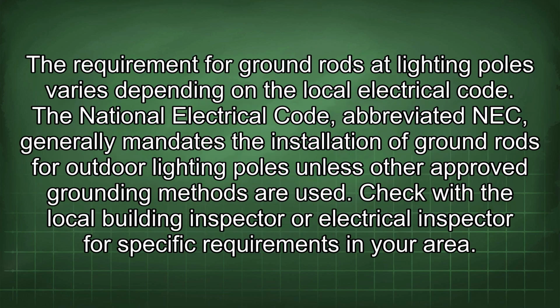The requirement for ground rods at lighting poles varies depending on the local electrical code. The National Electrical Code, abbreviated NEC, generally mandates the installation of ground rods for outdoor lighting poles unless other approved grounding methods are used. Check with the local building inspector or electrical inspector for specific requirements in your area.